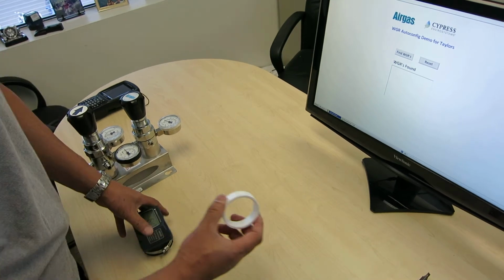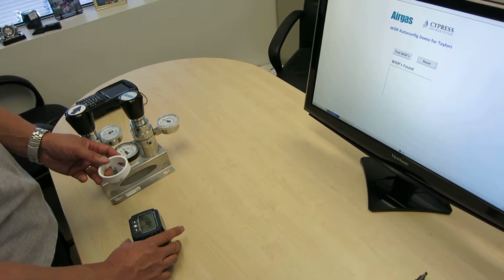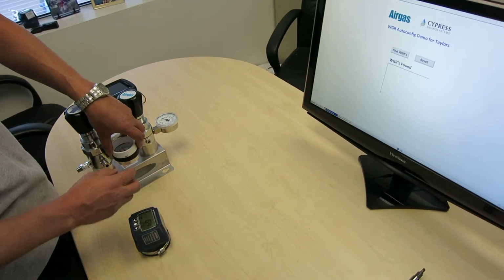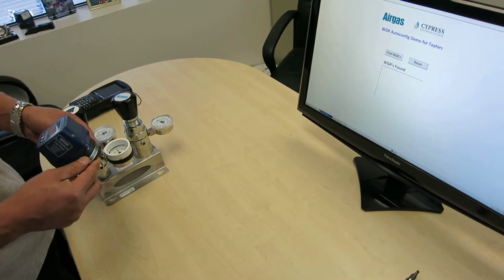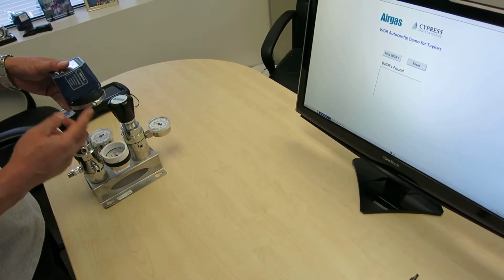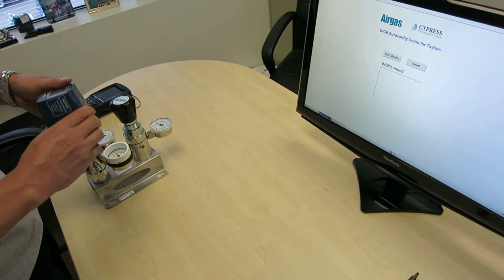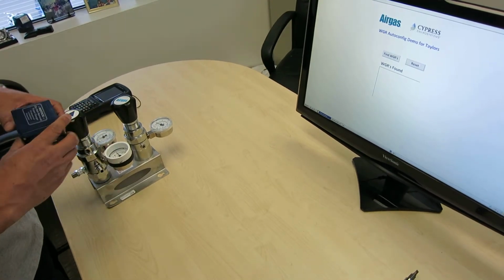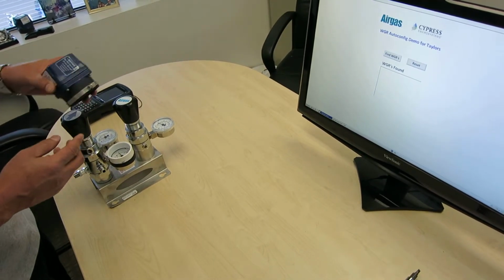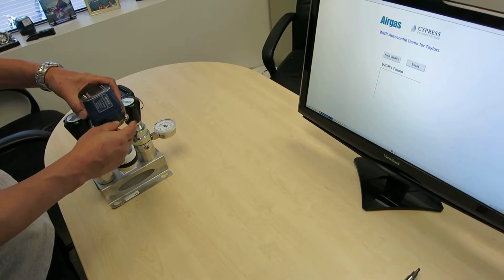Okay, now this spacer here is really important, because now we put the spacer on top, and what it does is make sure the gauge is always at a set distance from the gauge reader, not tilted and not too far in or out. So that's a big element in helping us do the standard calibration.